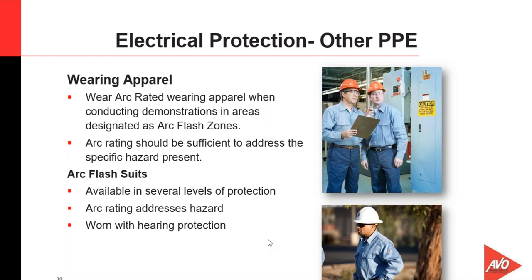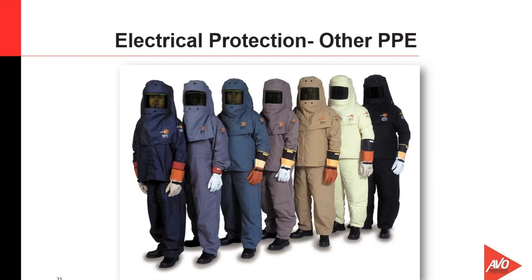A PPE level can use wearing apparel as part of that level with the addition of a face shield, a balaclava, and protection for the hands. The individual would have a category of flash protection, but you would have to add those other protective items to it. Arc flash suits, obviously, are rated for the extent of the hazard that's there, and all levels of flash protection need to be worn with hearing protection. This just shows a makeup of arc protection. It starts on the lower category on the left and goes all the way to the maximum available arc flash capability. Typically, most people wear about the middle of this as their maximum level, depending on the nature of their systems and the actual arc flash issues that they have in the workplace.